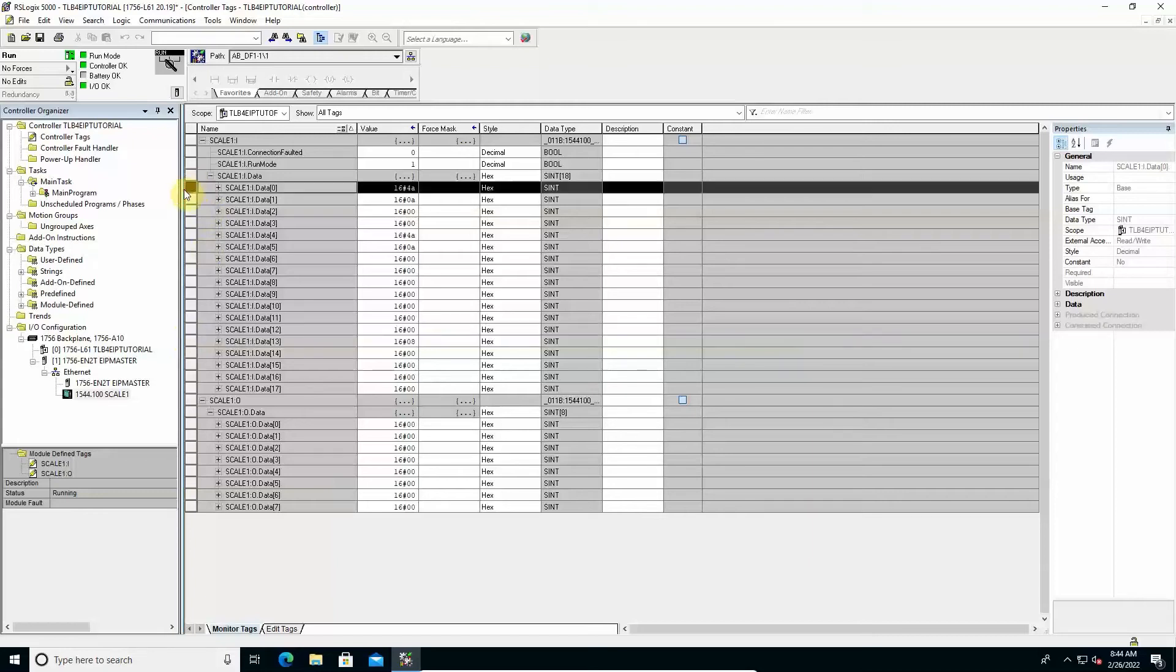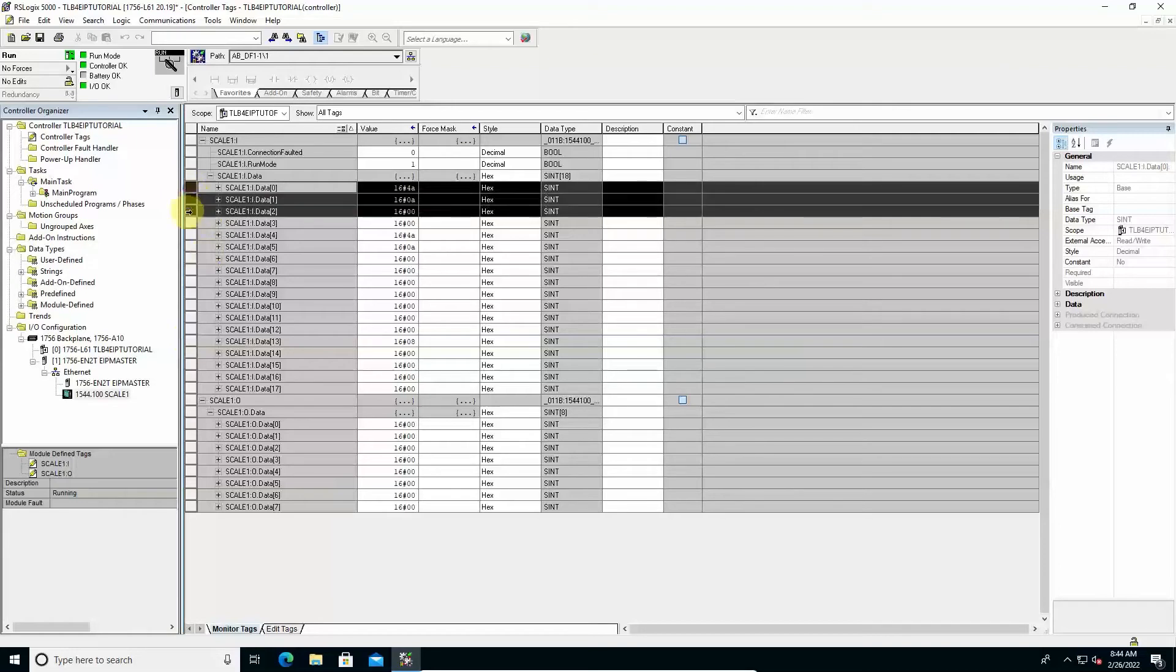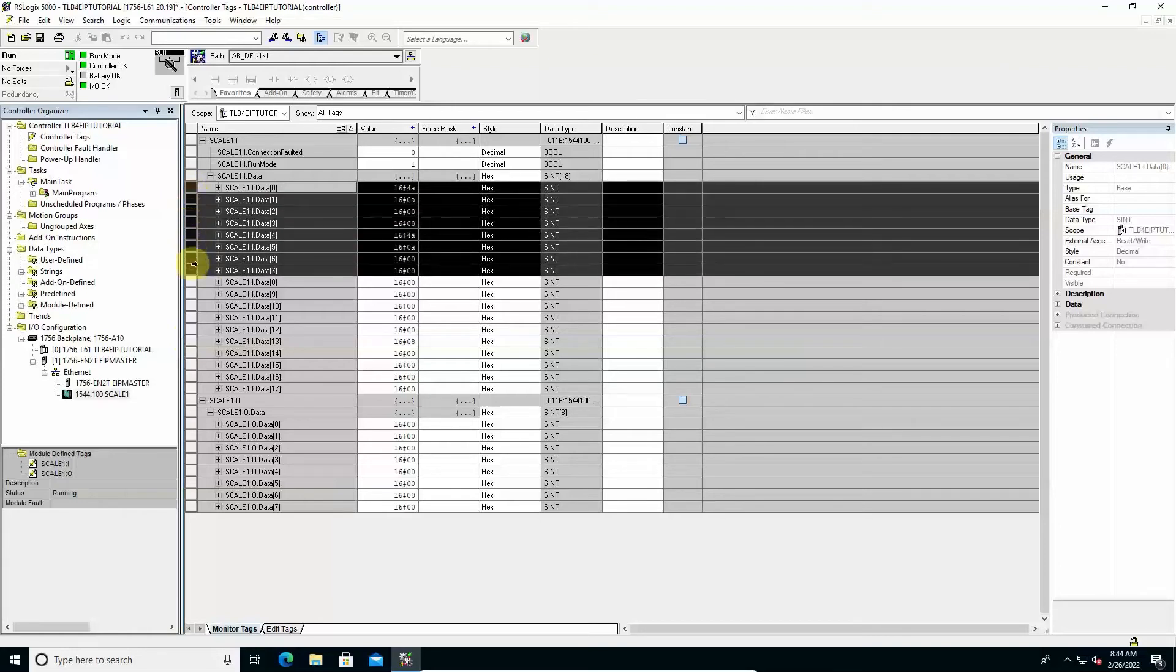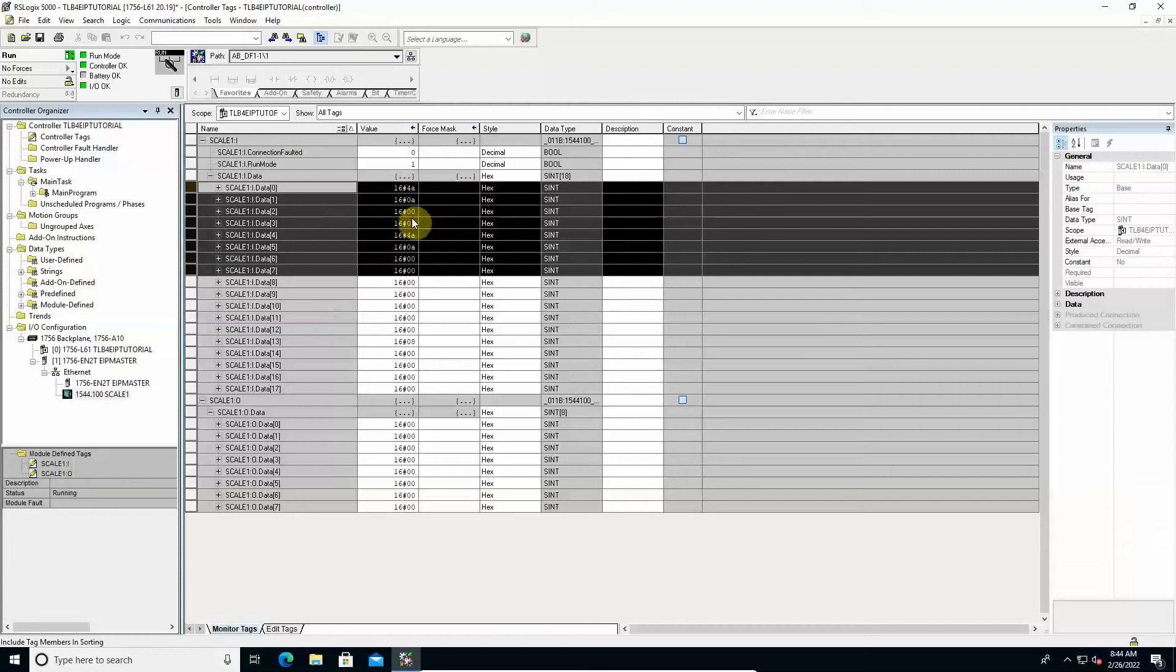With reference to the current values, some observations regarding the weight values management. The two values are currently identical because no tare is applied. For both of them, the absolute value is transmitted, including the decimals but without a decimal point. Each value is made up of 4 bytes.